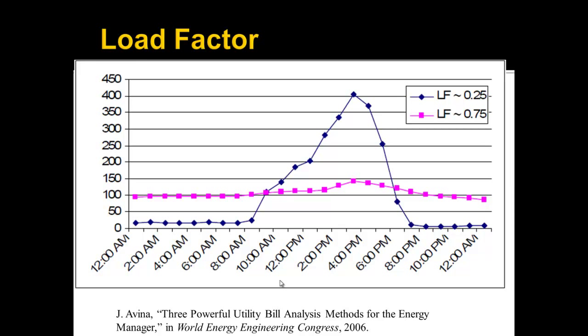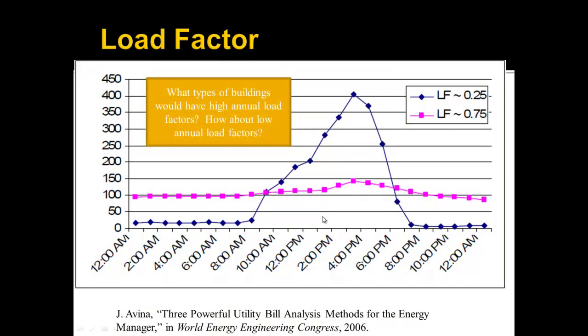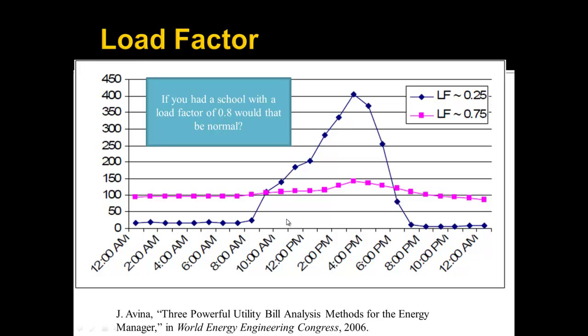So we covered EUI, ECI, and the ENERGY STAR score. Another thing you can do to compare your building's energy performance is the load factor — we talked about this a little bit in a previous class, but let's review. The types of buildings that have high annual load factors are very flat — that would be like a 24/7 convenience store, things that generally don't have a big peak. Low annual load factors are very peaky — something like a convention center that's only filled for a couple hours or days of the year. For a school to have a load factor of 0.8 would not be normal, because that means their consumption is rather flat and they're not really turning off their equipment at night.